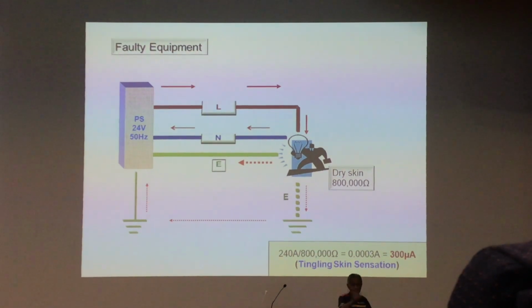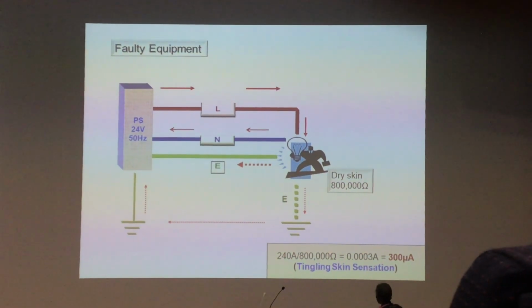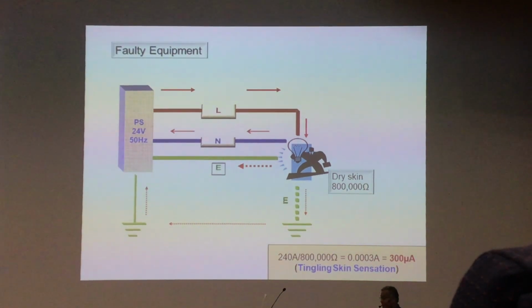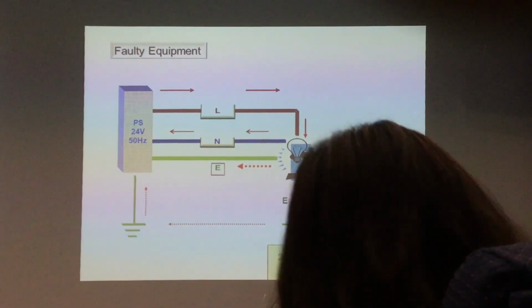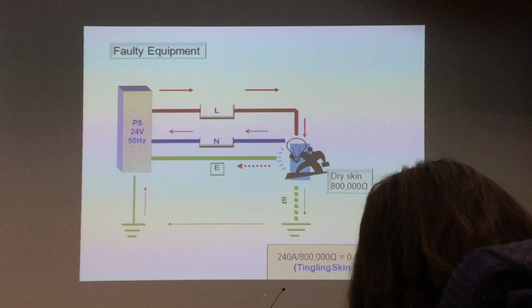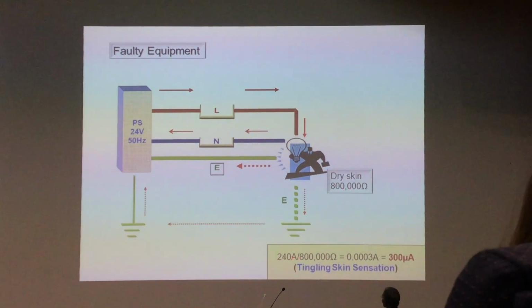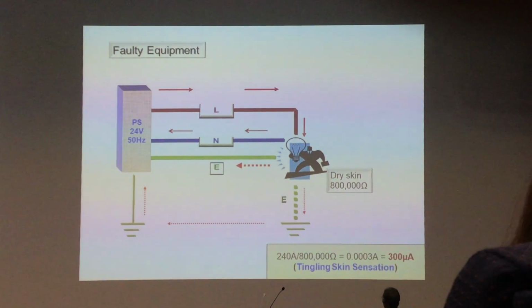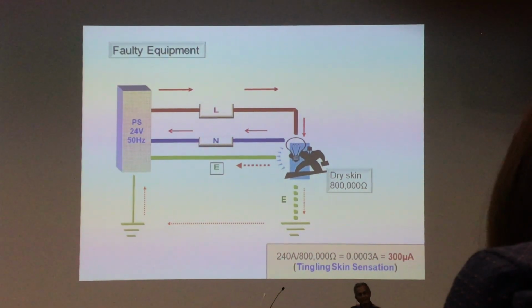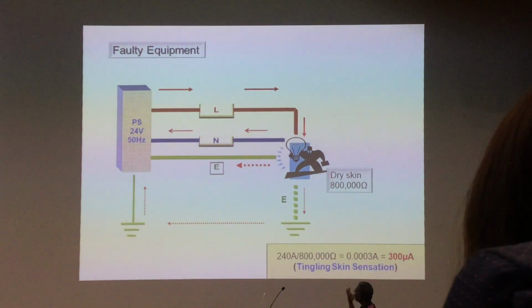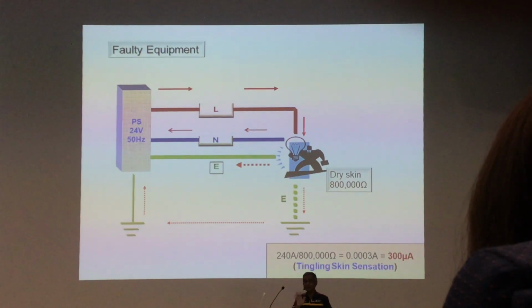Okay, let's say your hands are dry. The same machine is faulty. There's a leak, right? Maybe the wire is not properly connected, there's a break, or the wire was eaten by a rat or whatever. So the same current goes through your body, but your hands are dry, so resistance is very high, 800 kilo-ohms. So 240 divided by 800 kilo-ohms is 0.3 milliamp, 300 microamp. You touch it, just a bit of tingling sensation. You survive. So handling equipment with dry hands is important. Never ever touch equipment with wet hands, never ever in the OT.